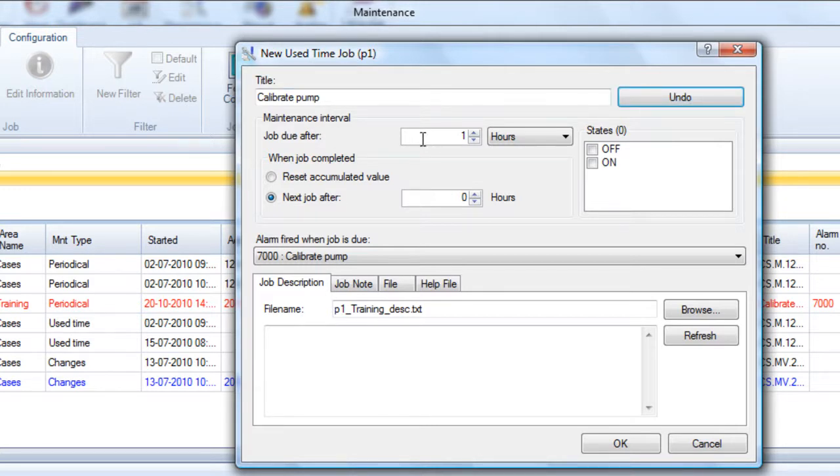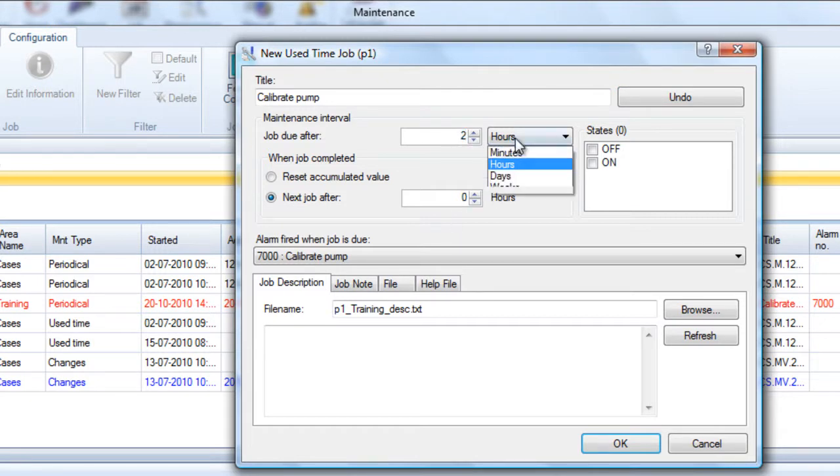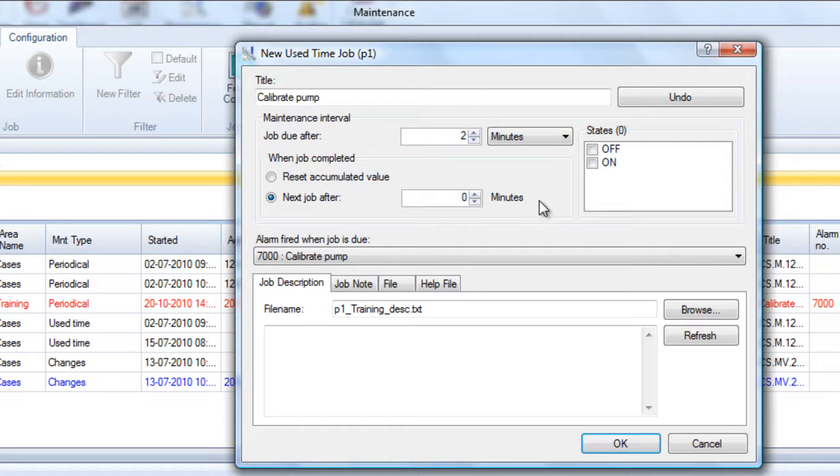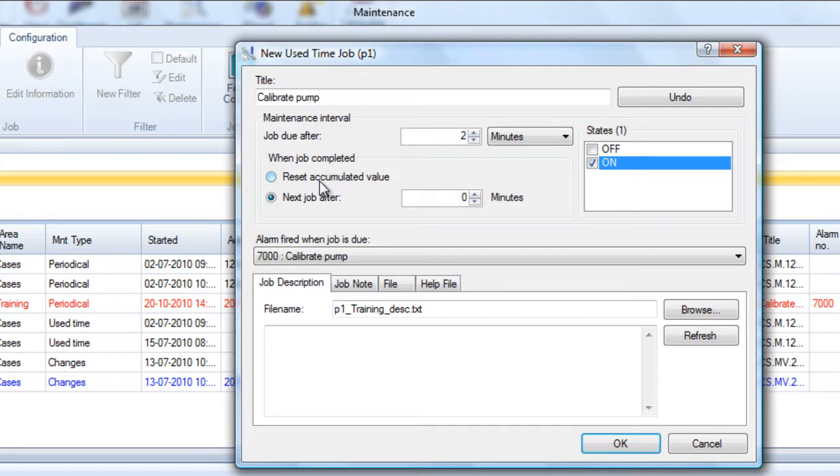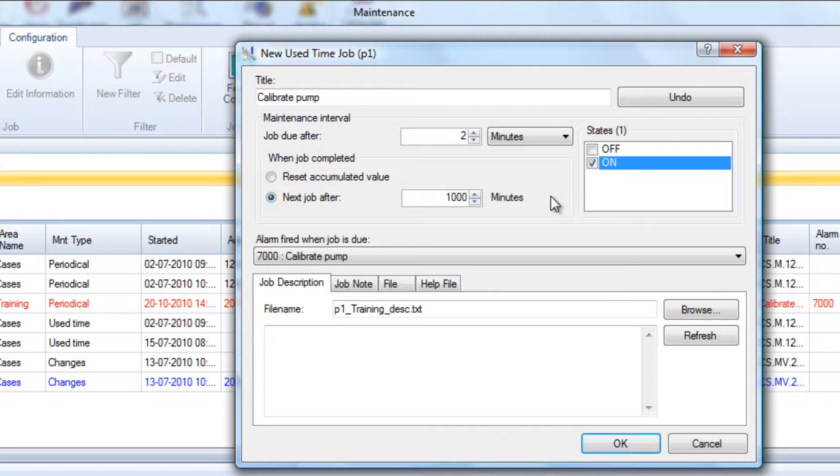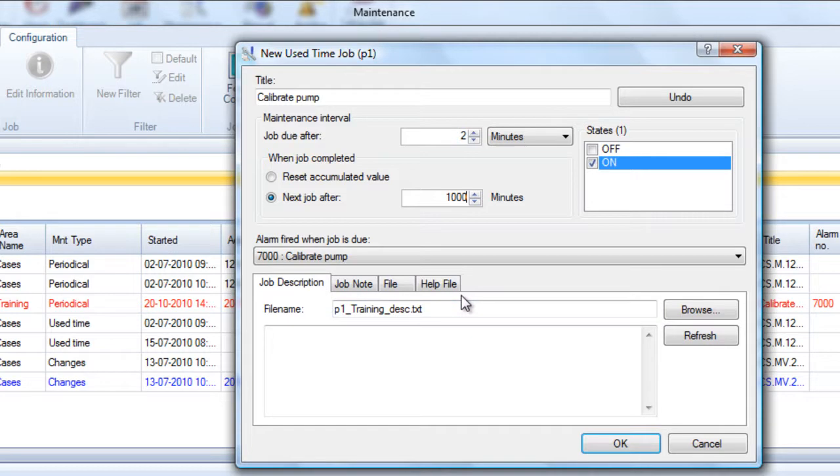Let's set up the job. Let's say that we want to calibrate after two minutes just to provoke it immediately. We only want to count when the pump is on, when it is running, so it's actually hours of operation that we're counting. After those two minutes we can reset the accumulated value to zero when the job has been completed by the end user, or we can tell the system to add a number of minutes. We could, for example, say that the next job after the two minutes is actually after a thousand minutes. That next job after interval will be the interval that will be valid until you change it in this dialog box.